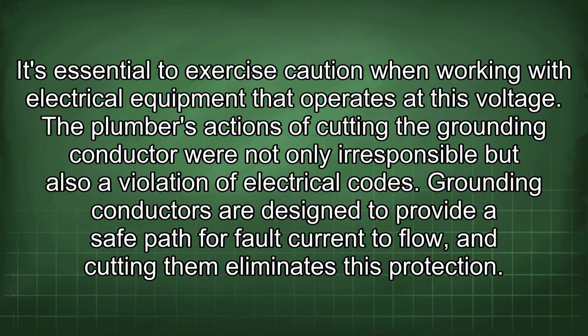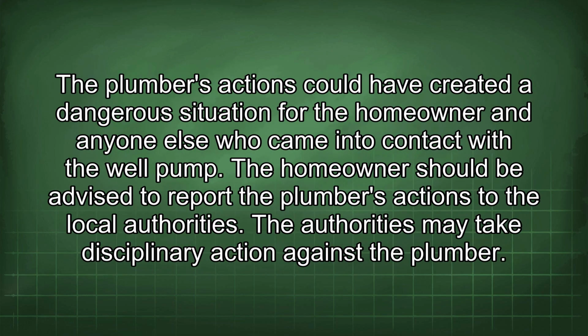The plumber's actions of cutting the grounding conductor were not only irresponsible but also a violation of electrical codes. Grounding conductors are designed to provide a safe path for fault current to flow, and cutting them eliminates this protection. The plumber's actions could have created a dangerous situation for the homeowner and anyone else who came into contact with the well pump. The homeowner should be advised to report the plumber's actions to the local authorities. The authorities may take disciplinary action against the plumber.